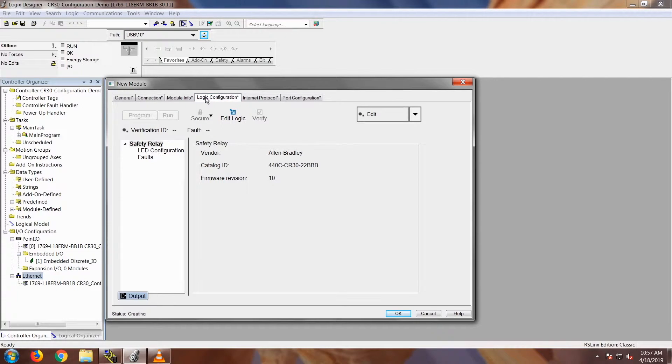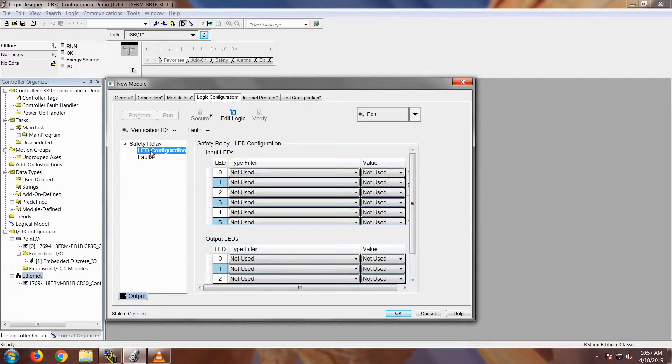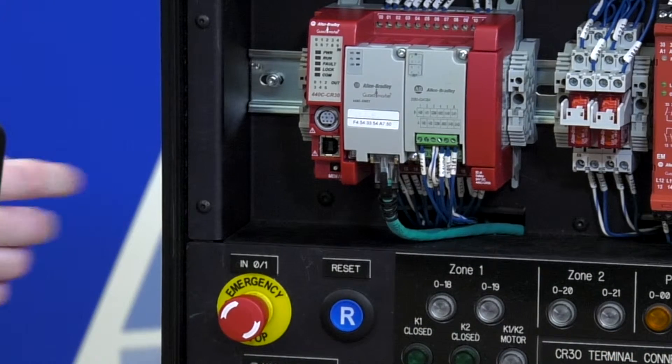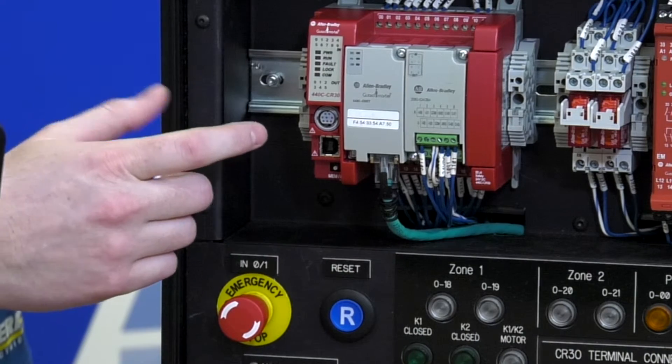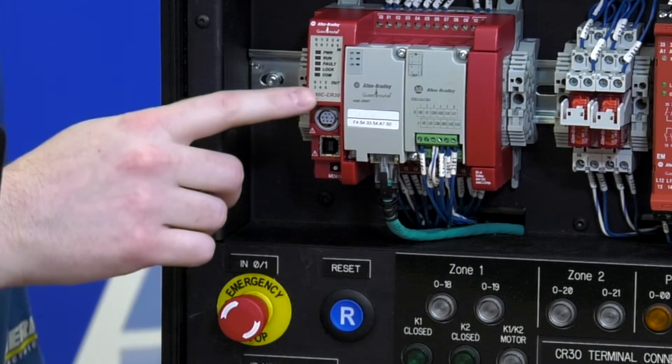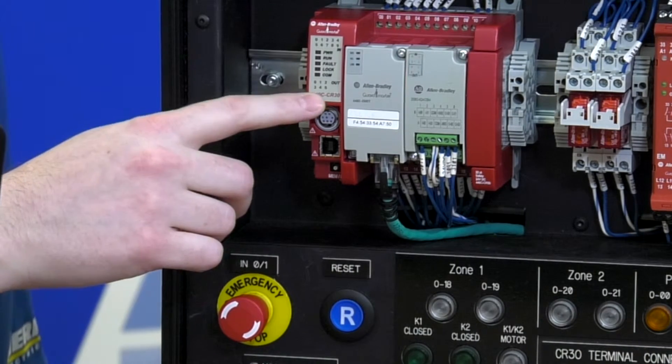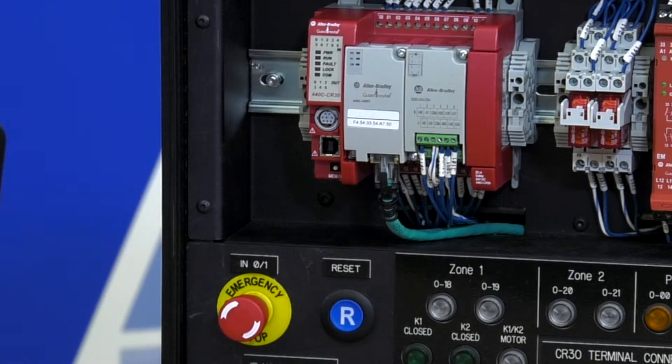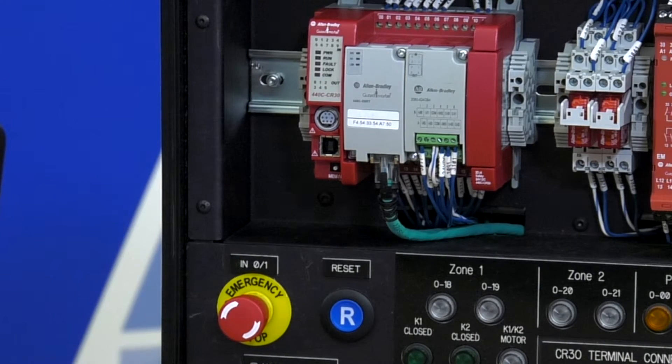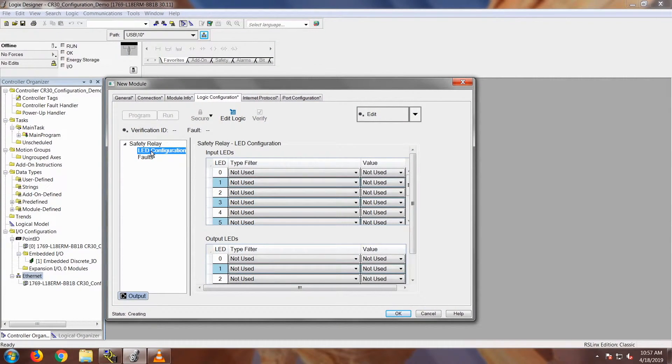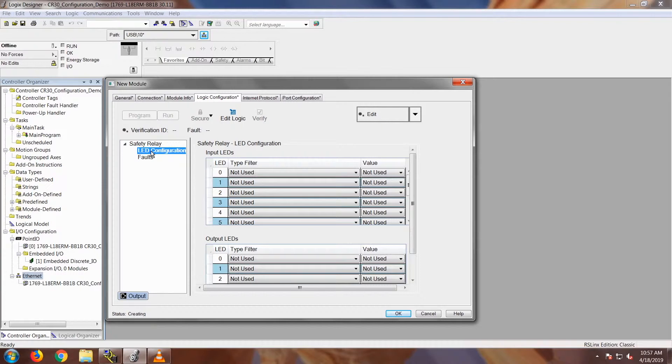Next tab is going to be the Logic Configuration tab that we're going to go over. If you notice underneath the Safety Relay button, if you highlight on LED configuration, this is where you actually configure the LEDs that are on the CR30. It's these 0 through 9, and your output LEDs are 0 through 5. This product is really the only product in the Rockwell family where the LEDs do not correspond to the actual input points of the CR30 itself. They are configurable.